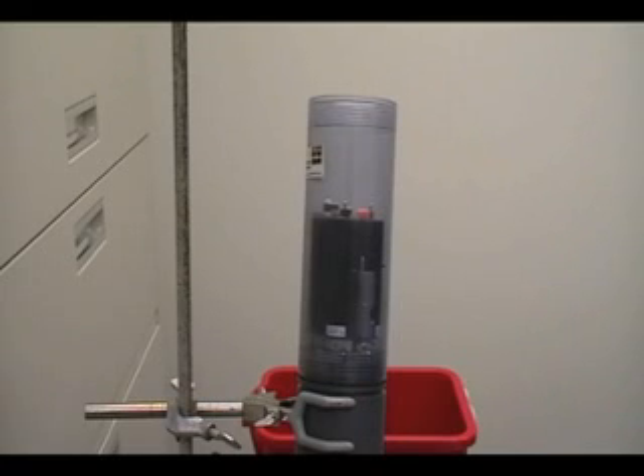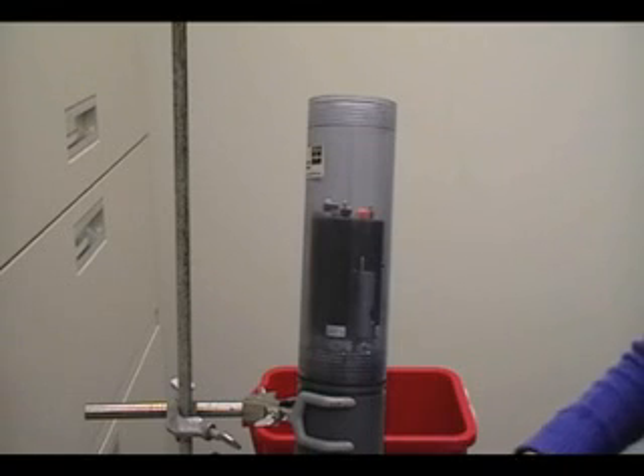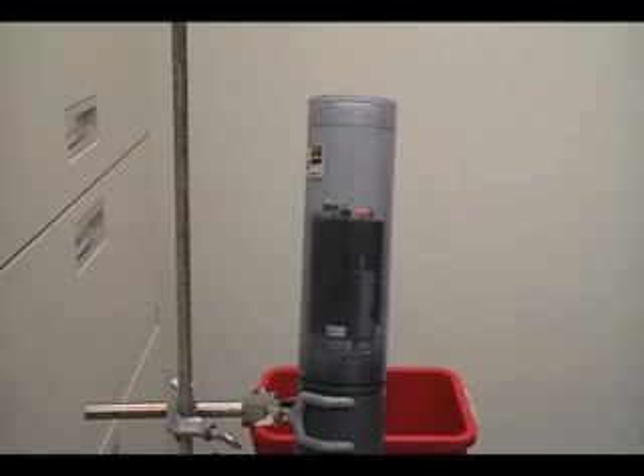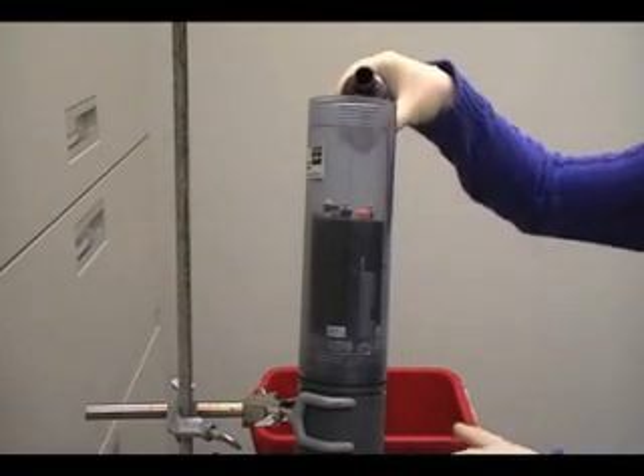Step 1. Prepare the ZoBell calibration solution according to the instructions on the bottle. Open the bottle and add 125 ml of deionized water to the dry powder. The solution has a half-shelf life of 6 months once mixed. Step 2. Rinse the sensors and calibration cup with deionized water and then some of the ZoBell solution. We have already completed these steps. Step 3. Pour the ZoBell solution into the calibration cup and immerse the pH and ORP sensor and the temperature sensor in the solution.